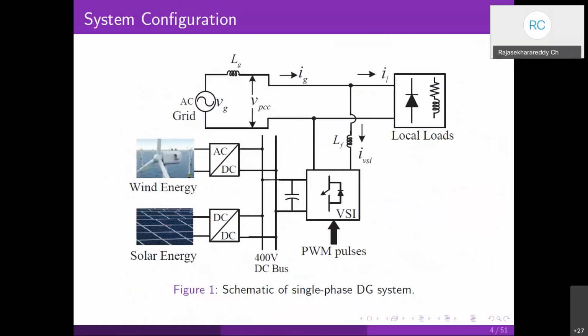Here it is a single-phase distributed generation system. I have considered it single phase to demonstrate the concept here. You see here we have a voltage source inverter. It is interfacing the renewable energy sources to the grid, and it is connected at the point of common coupling, where load and grid are meeting.